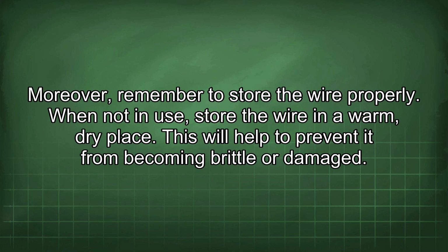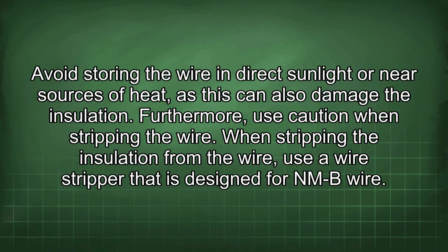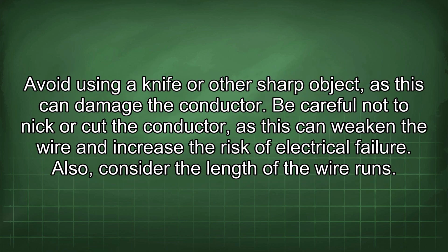This will help to prevent it from becoming brittle or damaged. Avoid storing the wire in direct sunlight or near sources of heat, as this can also damage the insulation. Furthermore, use caution when stripping the wire. When stripping the insulation from the wire, use a wire stripper that is designed for NMB wire. Avoid using a knife or other sharp object, as this can damage the conductor. Be careful not to nick or cut the conductor, as this can weaken the wire and increase the risk of electrical failure. Also, consider the length of the wire runs.